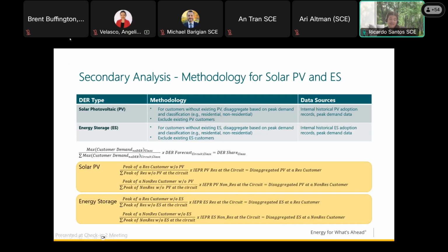These next three slides capture the details on data sources and methodology used to disaggregate the circuit level 2023 IEPR DER forecast to individual customers. For this first slide, solar PV and energy storage have similar approaches. For customers without existing PV or energy storage, the method is to disaggregate based on peak demand and customer classification. Existing customers with PV or energy storage are excluded. The main takeaway is that the computation gets you proportional to the forecast at the circuit to the structure level for each customer classification type. The general formula applies to all DER types, and these are the sets of equations for both solar PV and energy storage.